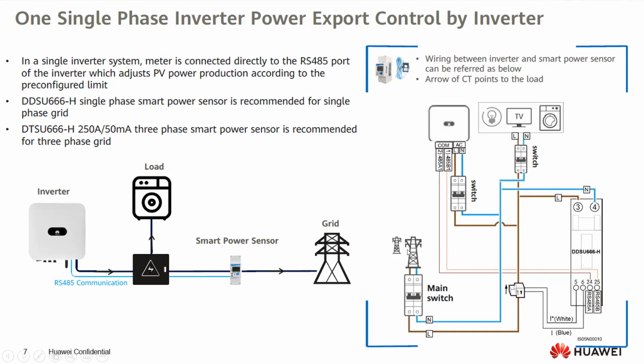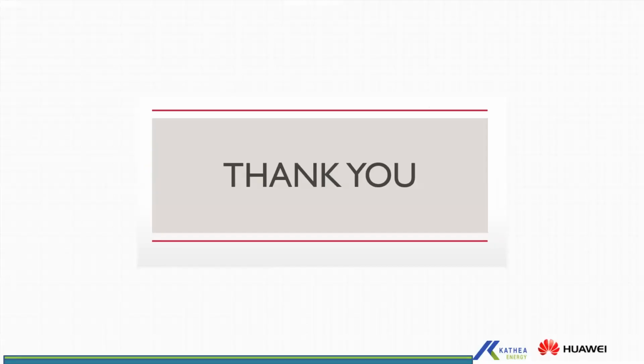So then the inverter will be able to monitor your grid, and the meter is a class 1, and it's compatible for export limiting. So the inverter can actually ramp down from max production to 0 within 5 seconds in cases of export control. So Tafi will take you through the commissioning setup. Do you have any questions in terms of wiring setup, product overview before we jump into commissioning?